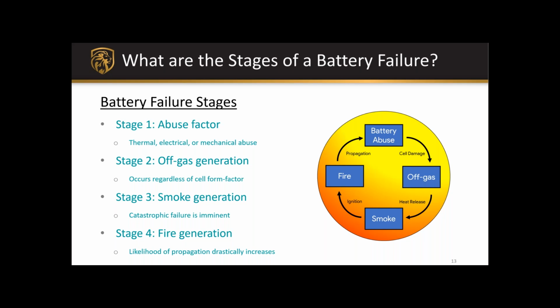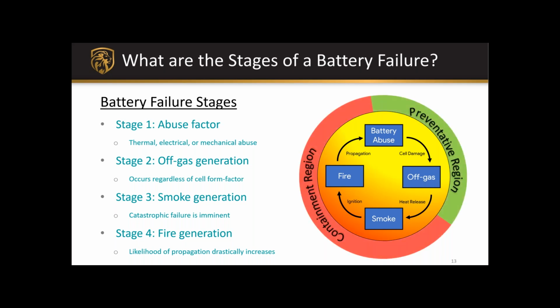If we look at this within 2 regions, we see 2 important areas. First is the preventative region, which happens before the cell is in thermal runaway. Then once that cell is in thermal runaway, we're into a containment region, where we have to deal with the effects and consequences of that cell being in thermal runaway.